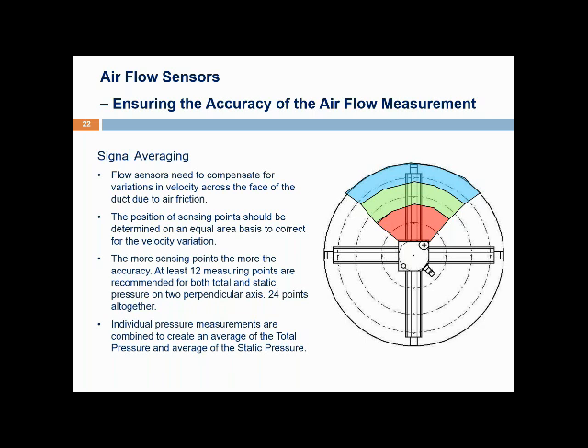To get accurate airflow measurements, it is important that the flow sensor measures the true averages of both total and static pressure, compensating for variations in velocity across the duct. Friction between air and the duct wall reduces air velocity closer to the wall, so the velocity profile varies across the duct. Sensing point positioning is very important — they should be positioned on an equal area basis to compensate for velocity variation. At least 12 measuring points are recommended for both total and static pressure on two perpendicular axes — making 24 measuring points in total. The individual measurements should be combined to create an average of overall total pressure and overall static pressure, yielding an accurate average velocity pressure and airflow rate.